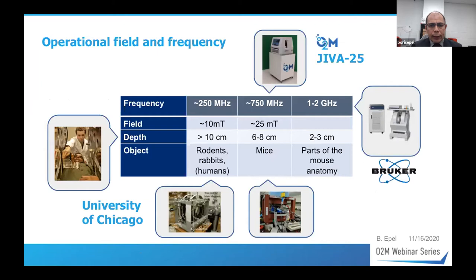The choice of frequency. Of course, from basic physics, you know that the signal will be increasing with frequency due to the Faraday law. And the Boltzmann distribution creates a bigger polarization for the higher frequencies. But unfortunately, with the increase of the frequency, the second effect kicks in. And this is the absorption. The water causes absorption of RF energy and this effect dramatically increases with frequency as well. So at some point, no RF can be penetrating inside the sample. And for each size of the sample, we are set to a particular range of frequencies. And one can argue that we can select an optimum frequency which is associated with each object size.